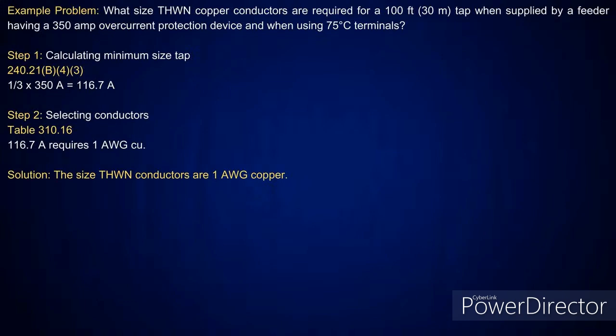You know, I can sit here and go on all day. The thing I want people to pay real close attention to: 10 foot or less, divide by 10. Everything else you take at a third. Don't care if it goes up to 100 foot. They may do a 100-foot tap thinking they'll trick you. Don't get tricked and fall into that. Pay attention to the basic rules that I'm giving you and tips to remember when you go in and you're going to take a test.